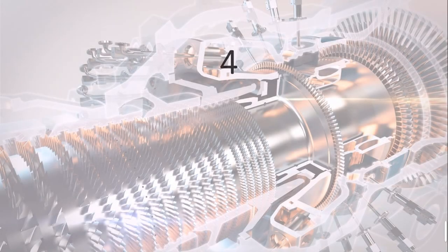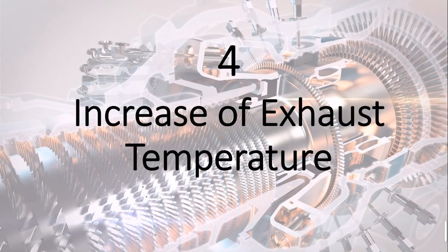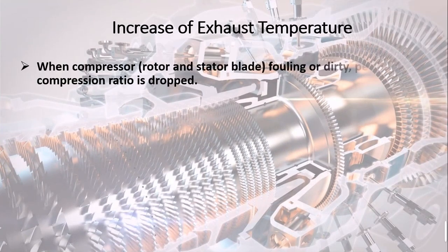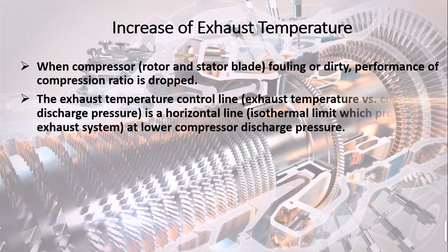Reason 4: Increase of exhaust temperature. When the compressor rotor and stator blades are fouling or dirty, the performance of the compression ratio is dropped. The exhaust temperature control line — exhaust temperature versus compressor discharge pressure — is a horizontal line, an isothermal limit which protects the exhaust system at lower compressor discharge pressure.